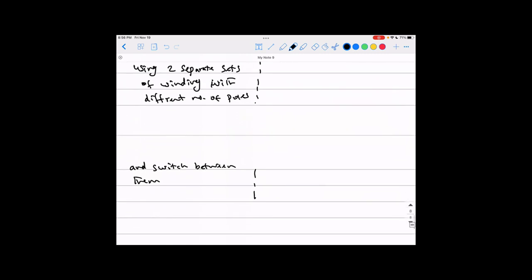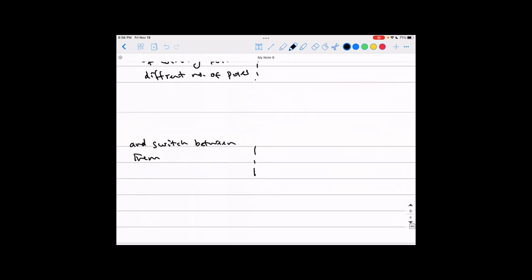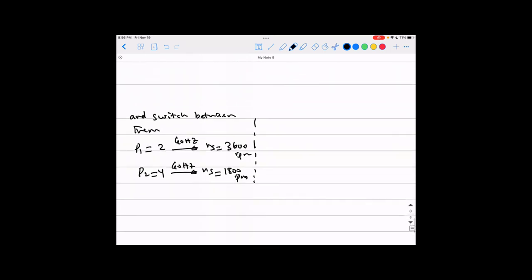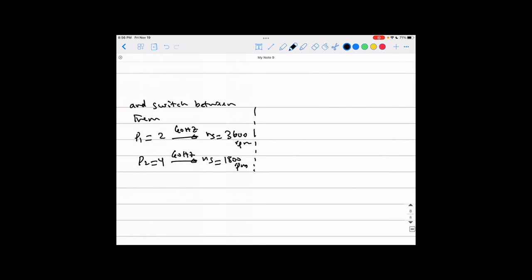With a two-pole winding at 60 Hz, the synchronous speed is 3600 RPM. With a four-pole winding at 60 Hz, the synchronous speed is 1800 RPM. You have two separate winding sets and you choose to connect one or the other to the supply, just by switching between them — and by switching you are controlling the synchronous speed by a very large amount.